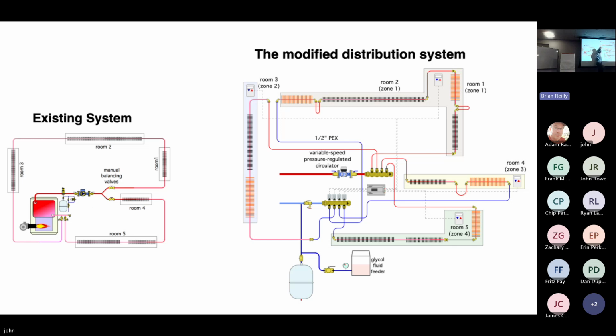So we're converting from copper over to 1/2-inch PEX tubing. And you might say, well, gee, that's 3/4 inch copper, you're converting it to 1/2-inch PEX. But remember now, we're creating 4 independent parallel circuits. We can do that. That will work just fine with 1/2-inch PEX. And then we put in a manifold, just like they use for floor heating. Some of the manifolds can be equipped with what are called manifold valve actuators. These are little 24-volt motors that open and close the valve. It's built into each circuit position in the manifold.